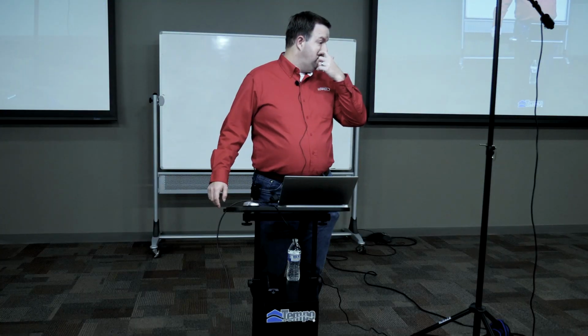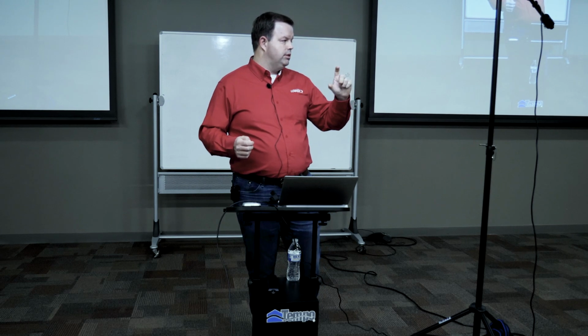The main thing I bring up about the discharge air sensor is that sometimes, if you see an issue where a system is overcooling, let's say it's freezing up a zone, or if it's cutting out on high limit, sometimes that can be an issue of where that discharge air temp sensor is. It can be thinking that your discharge air temperature is a lot warmer or a lot cooler than it actually is. And so it can overcool the evaporator or overheat your heat exchanger trying to heat up that discharge air temp. So it's just critical to make sure that's an area that's getting an accurate reading if you're seeing some misbehavior.